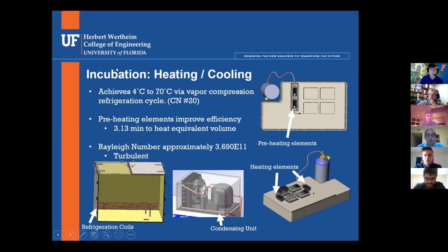Another part of the incubation subsystem includes the heating and cooling of our overall incubation. And so the heating and cooling system is able to achieve a temperature range from 4 degrees Celsius to 70 degrees Celsius, and it's modeled after the vapor compression refrigeration cycle. So this satisfies customer need number 20.